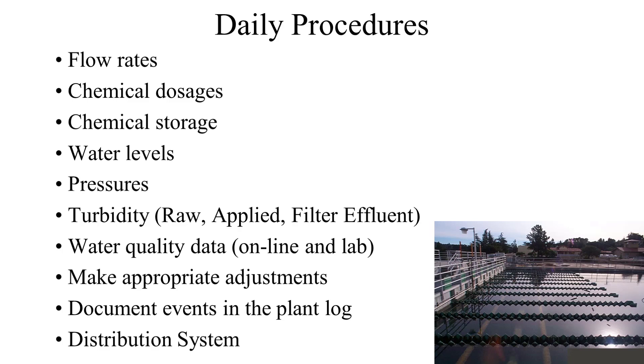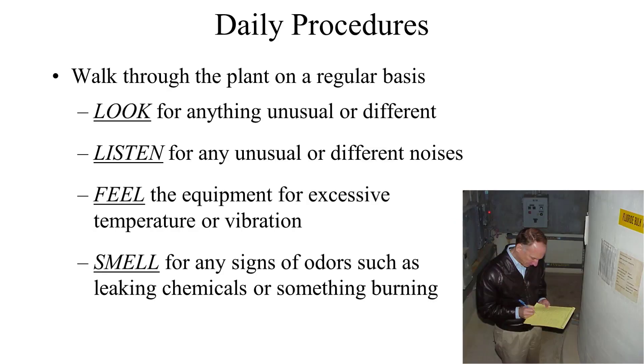Monitoring the distribution system is also important to anticipate any changes to the plant flow rate or recognize a problem in the system so the plant is prepared to meet distribution system demands. Another important duty of an operator is to periodically walk through the plant and look for anything unusual, such as a sparking wire or a pump that is out of service. Listen for any unusual noises such as a whining or banging noise that could indicate a problem with a pump. Feel the equipment as you walk by — is it excessively hot, cold, or vibrating more than normal?